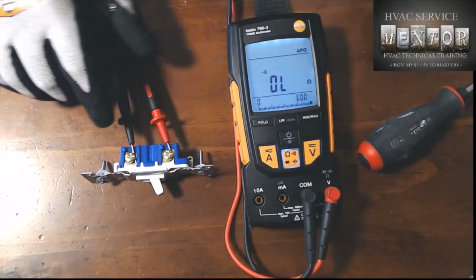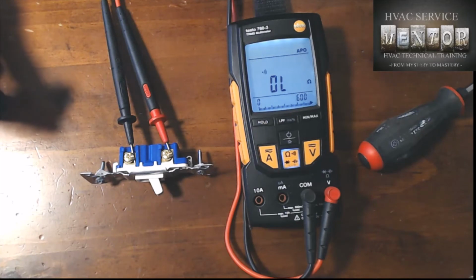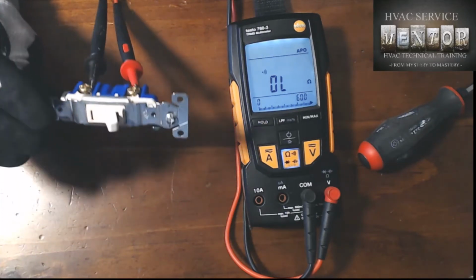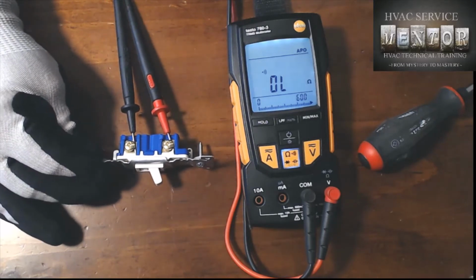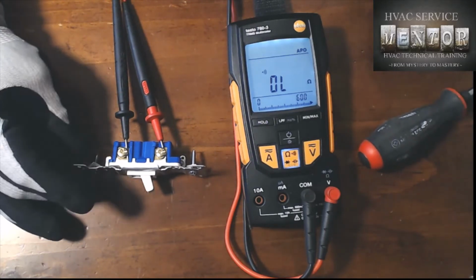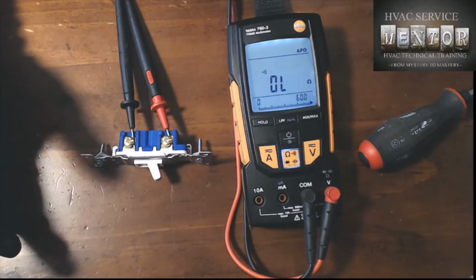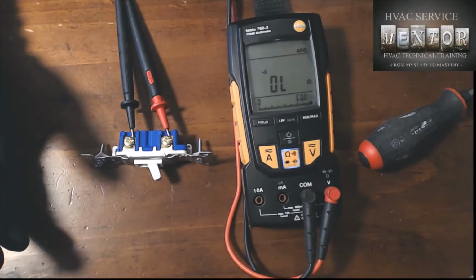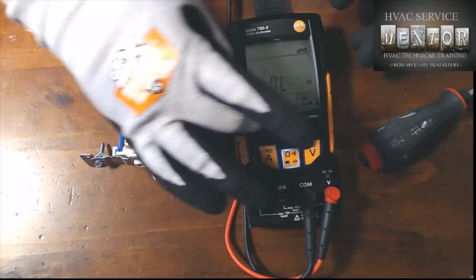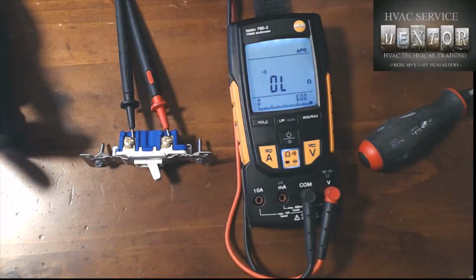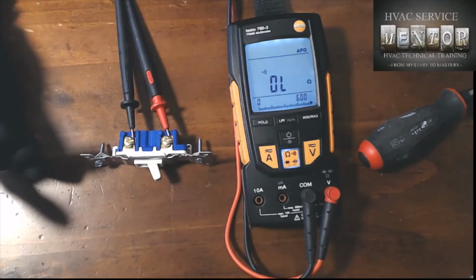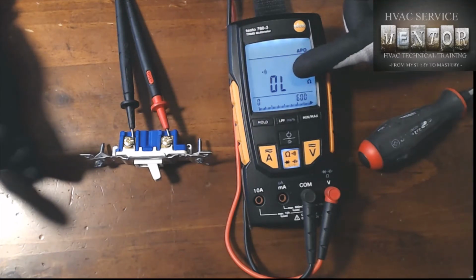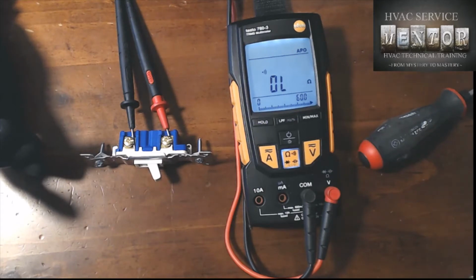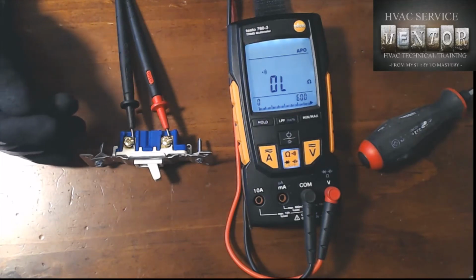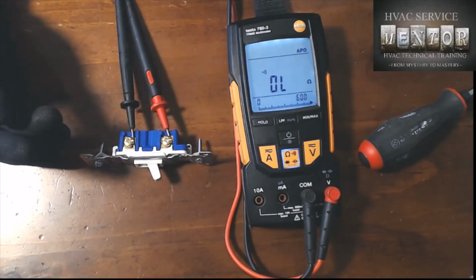So now I have my meter installed on the switch as if it was a pair of conductors. This toggle switch has the on and off designation, but when we talk about switches in machinery, we don't usually want to say the words on and off anymore. We want to use the terms open and closed. Right now we are in an open position because we are not experiencing the tone or the sound of continuity, and the multimeter is displaying OL, which means very high resistance. Remember, when the switch contacts are open, the electrical switch has very high resistance, like an insulator, and will not allow current to pass through.